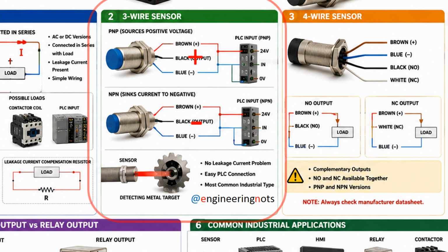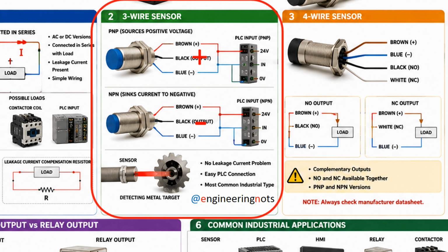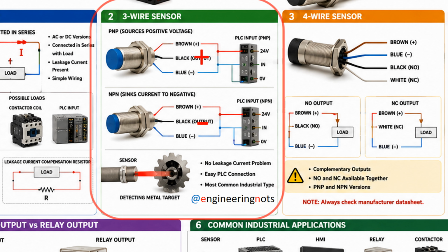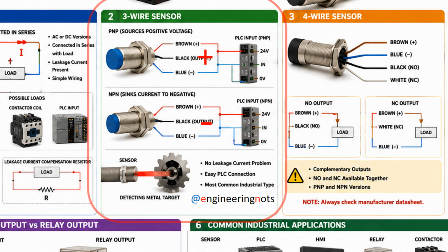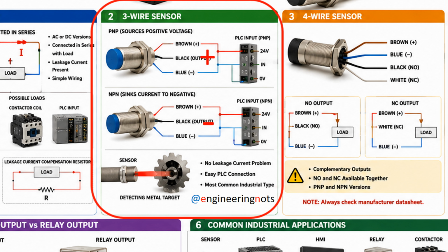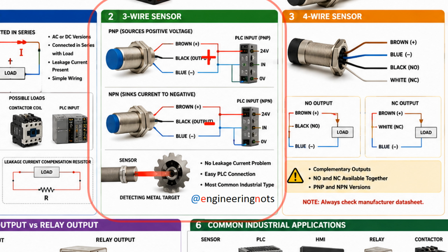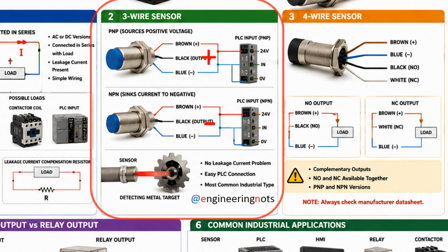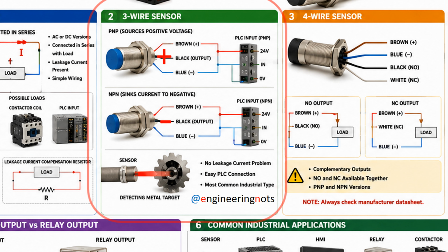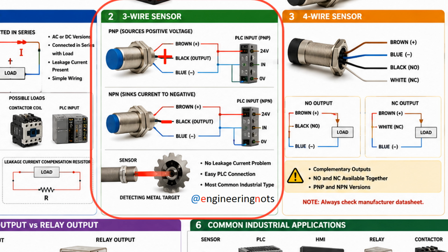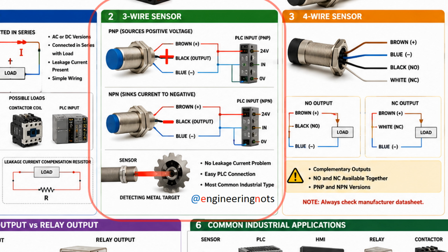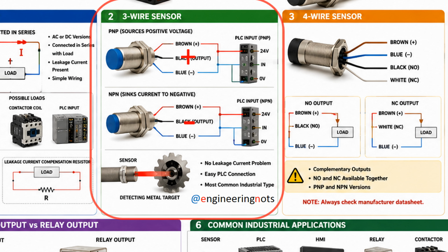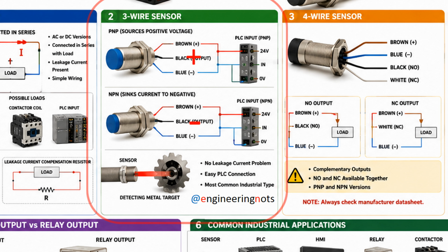To overcome the limitations of two-wire sensors, three-wire sensors were developed. Today, this is the most common type of industrial sensor used in factories. Standard wiring. In most well-known brands, brown wire, positive supply. Blue wire, negative supply. Black wire, output. However, the manufacturer's datasheet should always be checked. Why are three-wire sensors more popular? In these sensors, the power supply is separated from the output circuit. As a result, the leakage current problem is almost eliminated. Connection to a PLC also becomes much easier.